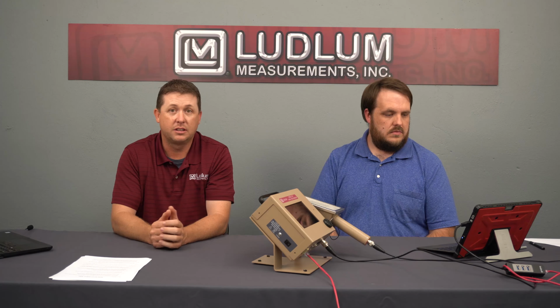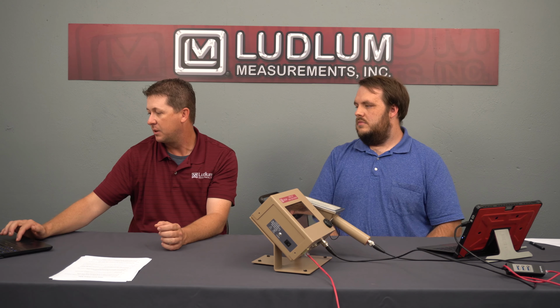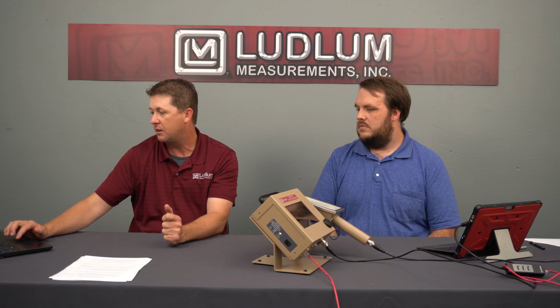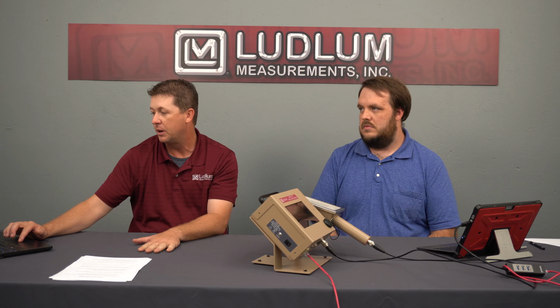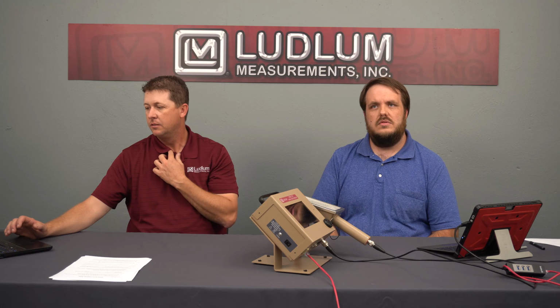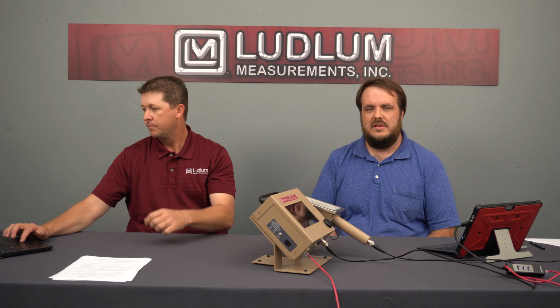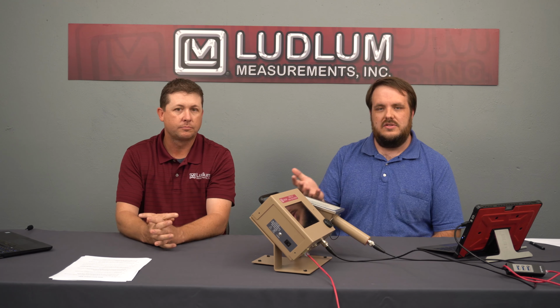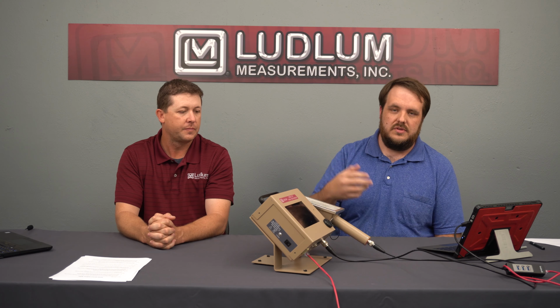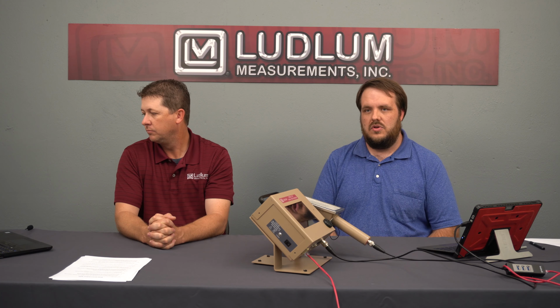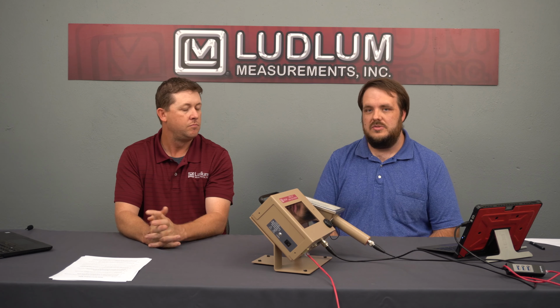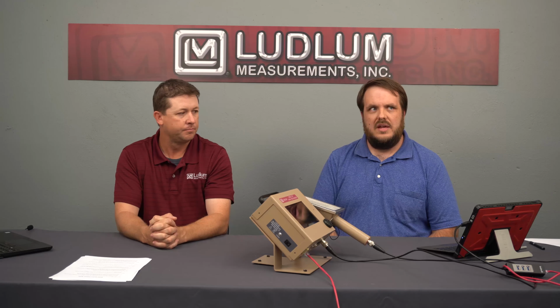So I have one here that says that I can see that the display is in CPM. Is it possible to display becquerel per centimeter squared or becquerel, etc.? I think you can set it to becquerel. It's limited to the settings you can set on a 3002, because whatever settings you set for the 3002's calibration, that's what this will display. 3002s don't currently have a becquerel per square centimeter specifically, but I believe they have becquerel. It does have becquerel, DPM, becquerel, CPM.